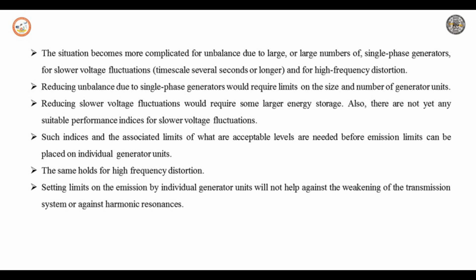Setting limits on the emission by individual generator units will not help against the weakening of the transmission system or against harmonic resonance.